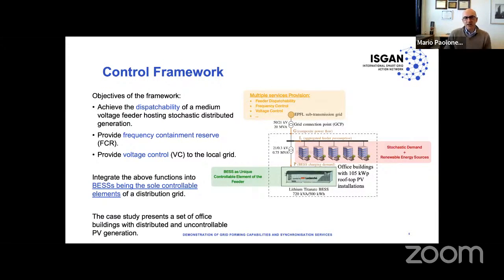The objectives of the control framework we developed are to achieve the dispatchability of a local medium voltage system—in our case, one of the feeders of the EPFL campus, which hosts a substantial amount of stochastic, non-controllable distributed generation and loads—and at the same time provide frequency containment reserve to the main grid, as well as voltage control to the local grid. Since your battery converter can work on four quadrants, you can also use this feature to provide reactive support to the local grid.